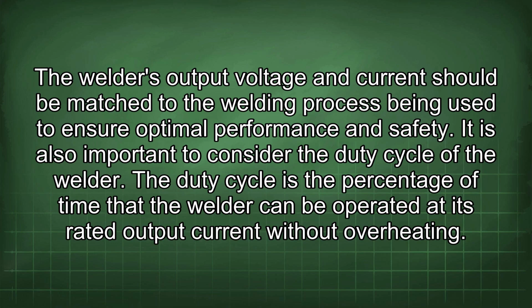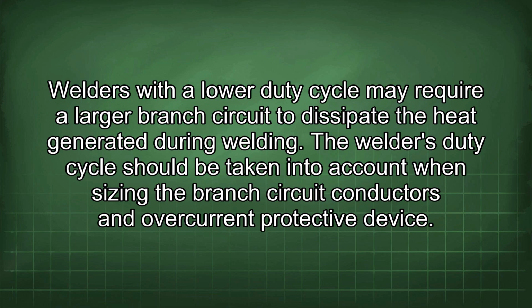It is also important to consider the duty cycle of the welder. The duty cycle is the percentage of time that the welder can be operated at its rated output current without overheating. Welders with a lower duty cycle may require a larger branch circuit to dissipate the heat generated during welding. The welder's duty cycle should be taken into account when sizing the branch circuit conductors and overcurrent protective device.